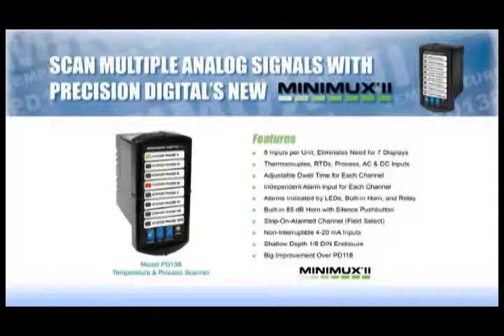As I demonstrated, alarms are indicated by a flashing LED, a built-in horn, and a relay. The PD-138 can also handle 4 to 20 milliamp signals, and is available with a resistor network that keeps the loops that are not currently being scanned from going open. This is useful if you are monitoring level in tanks from 4 to 20 milliamp level transmitters.